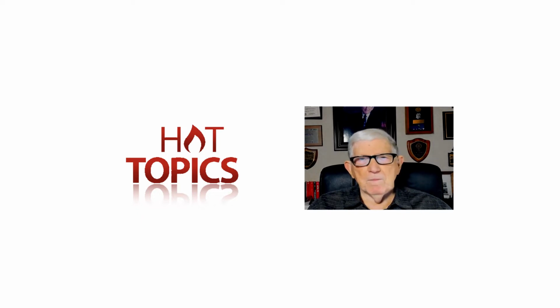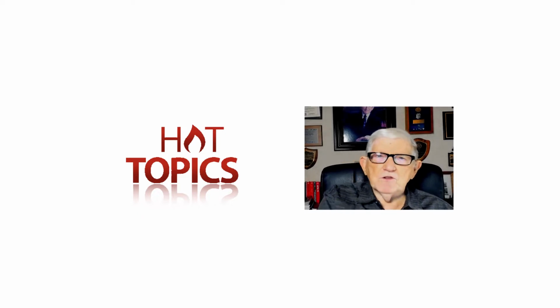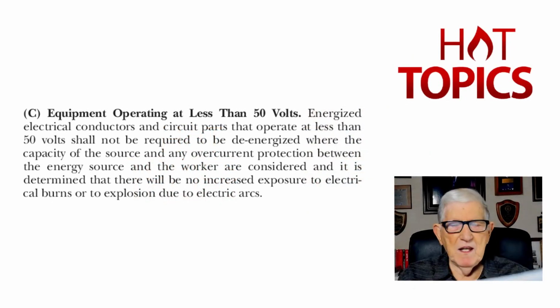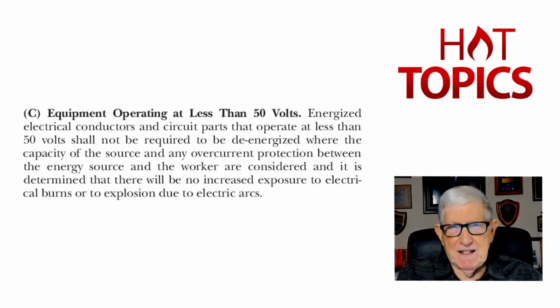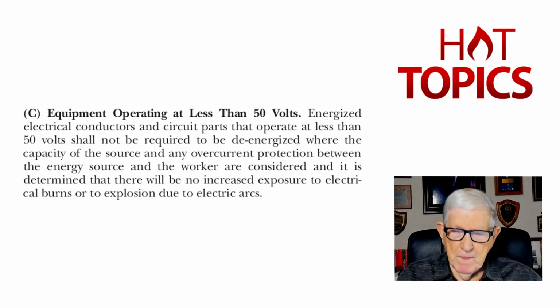130.4 EA. Now, I basically said, well, the first thing you have to do to really understand that, and you and I, it doesn't matter if we're engineers or electricians, we still have to know about this low voltage. Now, first of all, we want to go to NFPA 70E, the 2021 edition, and we want to look at 110.4C as in car, and it's equipment operating at less than 50 volts.